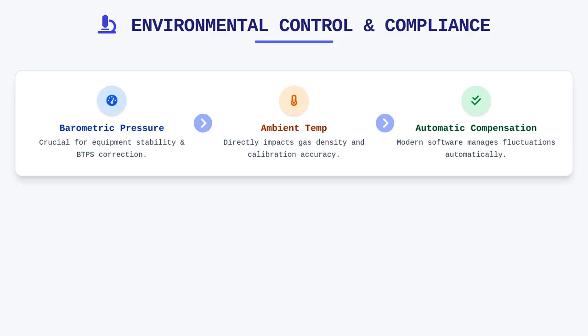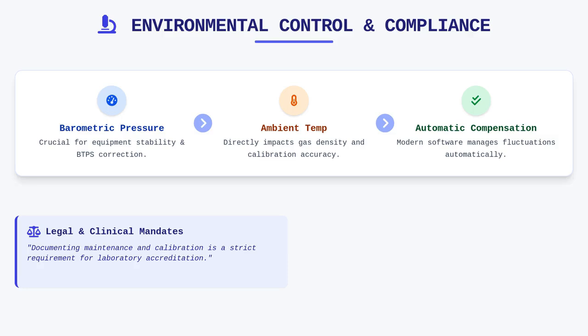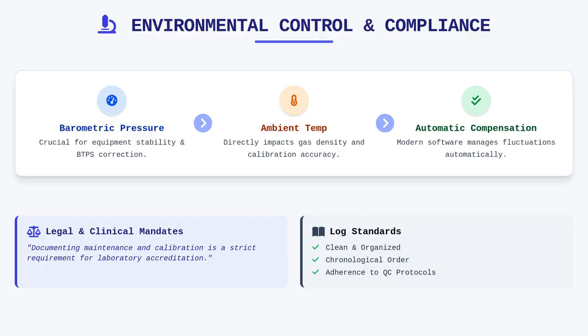If the ambient temperature varies significantly throughout the shift, your calibration records must reflect these shifts as gas density changes with temperature. Furthermore, documenting every maintenance event and calibration check is not just a best practice. It is a clinical and legal requirement for laboratory accreditation. You should maintain a clean, organized, and chronologically ordered log that demonstrates a continuous adherence to the established quality control protocols.